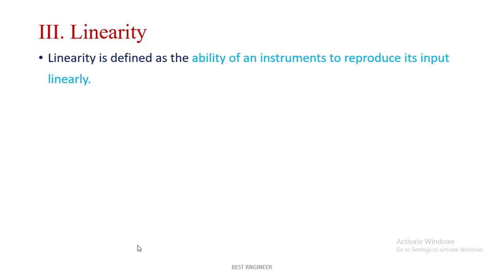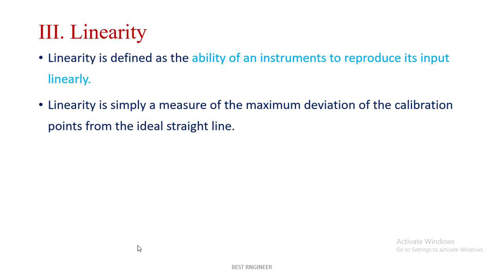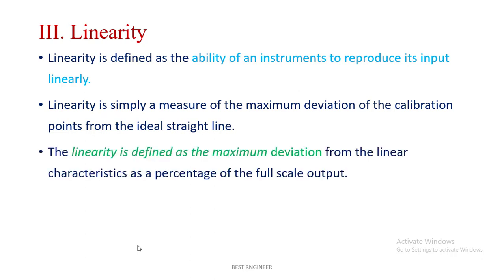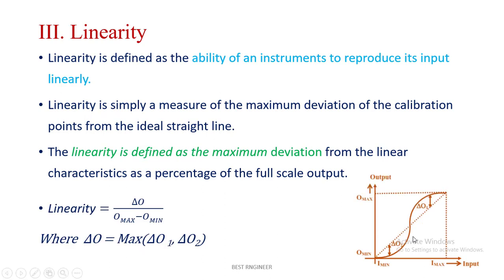Linearity is defined as the ability of an instrument to produce its output linearly. It is simply a measure of the maximum deviation of the calibration points from the ideal straight line, expressed as a percentage of the full-scale output. Looking at this picture, this one is the ideal line — the output varies with respect to the input — and this one is the real line. They will not coincide due to error. Linearity is calculated as Δo (maximum deviation of output) divided by the full-scale output difference.